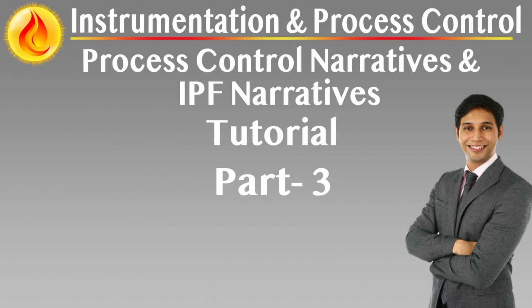Treatment of operational messages. If an alarm condition does not lead to an operator action or only rarely does, this should be explicitly stated, e.g. no operator action, informational only. In such cases, the alarm may be reclassified as an operational message or suppressed to reduce alarm flood and improve operator focus.